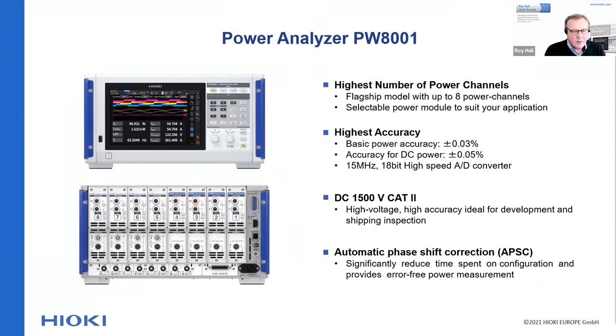The basic accuracy of the PW8001 at 50 to 60 Hertz is 0.03% and 0.05% for DC measurement. The highest sampling frequency is 15 megahertz, and the AD conversion has a resolution of 18-bit. It can measure up to 1500 volts in a Cat 2 environment, compliant to the latest IEC standards. In combination with the latest generation of current sensors, it has automatic phase shift correction function, APSC. This unique feature reduces the setup time and eliminates phase errors, regardless of the frequency and power factor that the instrument is measuring on.